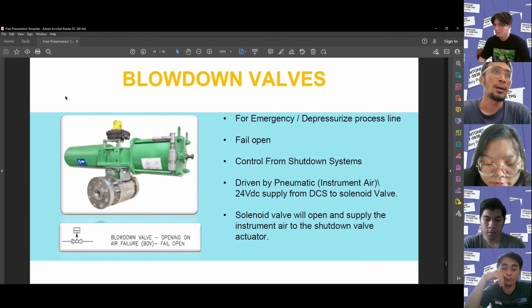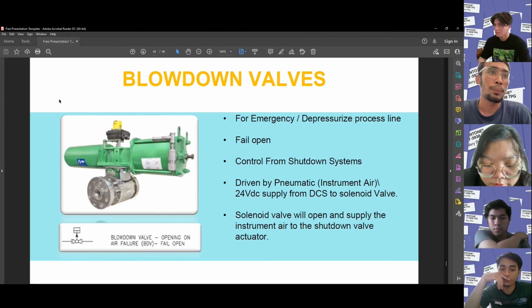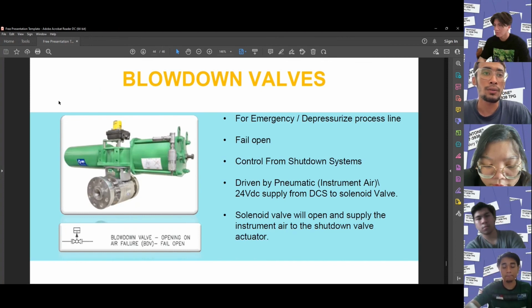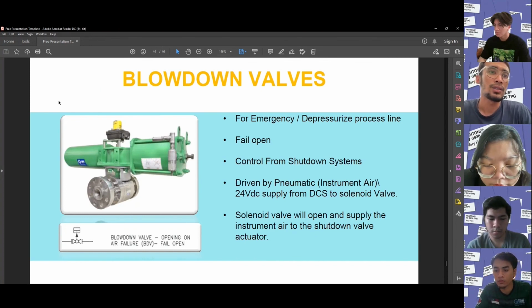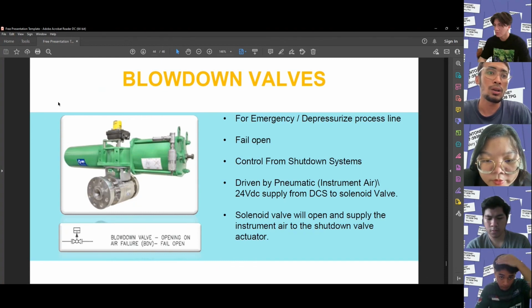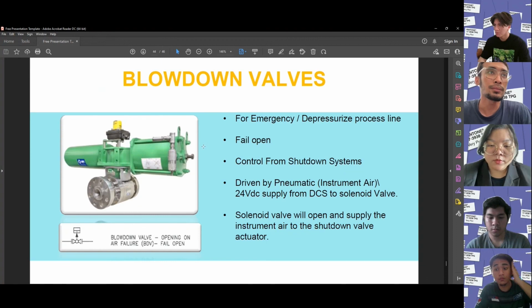Next, blowdown valve for emergency and depressurizing the process line. Second, fail open, control from shutdown system, driven by pneumatic instrument air or 24 volt DC supply from DCS to the solenoid valve. And the solenoid valve will open and supply the instrument air to the shutdown valve actuator.